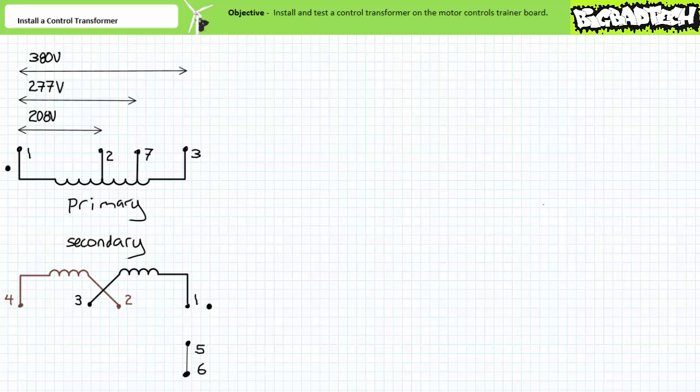Pilot level voltage, among its many flavors, can either be 24 volts DC or 120 volts AC. For the purposes of this application, we're going to wire up the previously installed control transformer to step down the 208 volt line-to-line voltage of a light industrial three-phase AC system to 120 volts AC. This would necessitate a step down transformer with a primary to secondary winding ratio of 1.73 to 1.